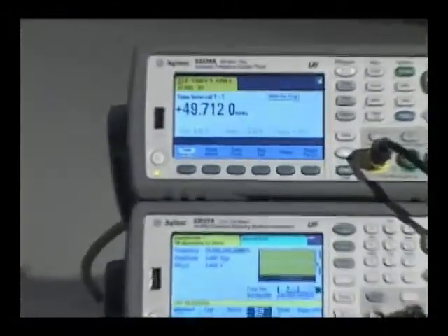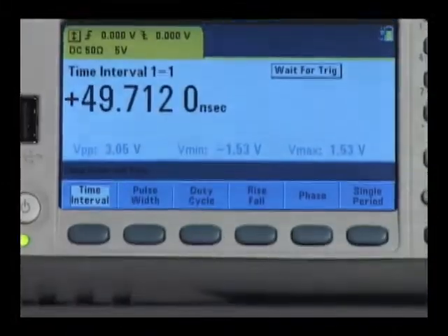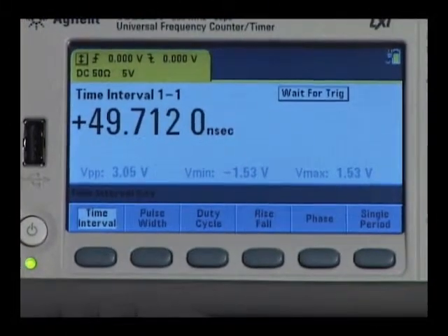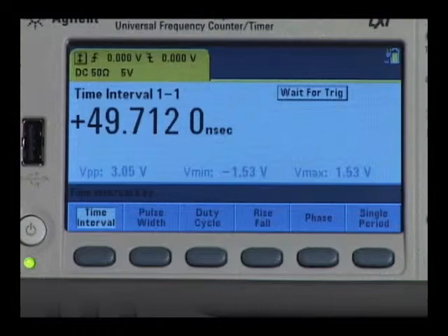I'd like to show you how to analyze clock jitter using unique features of the Agilent 53230A counter: statistics and histogram. Let's move to the front panel. The instrument is set up for time interval measurements, taking 10,000 readings.